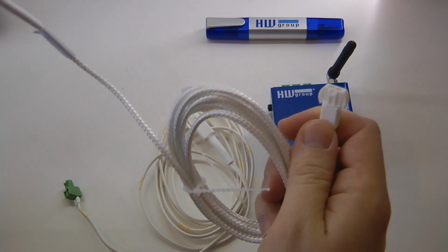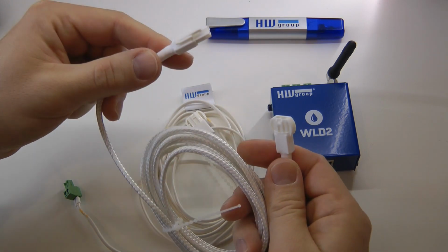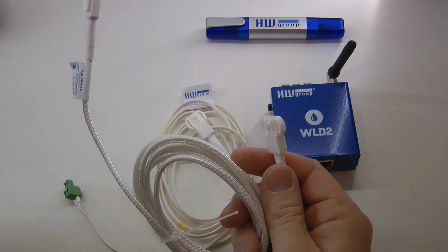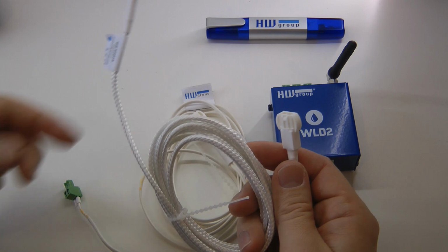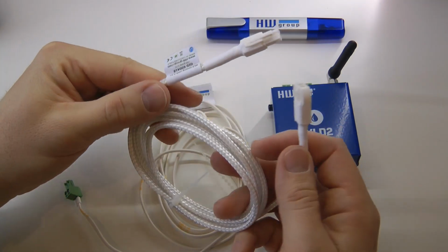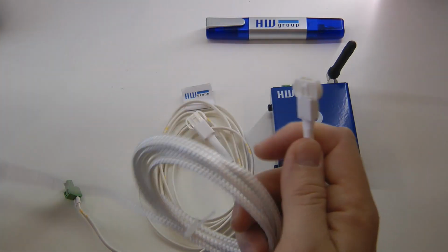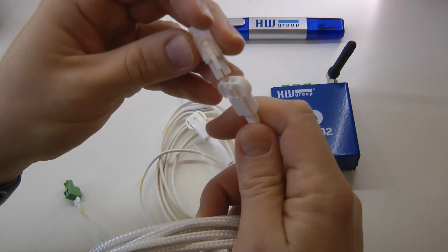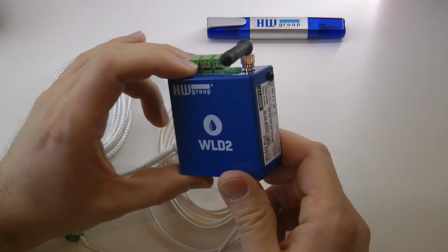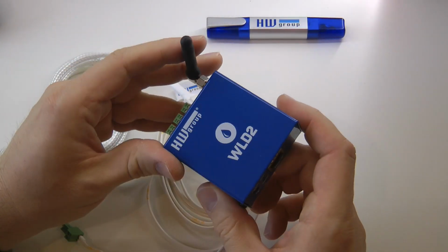And you can plug multiple of these cables together. So if you need to detect along a wall which is, let's say, 4 meters long, you can buy an additional detector cable and just plug the two together, and you always have to put this terminator plug at the end of the line. We talked about the actual detection quite a lot already, so let me talk about the device.